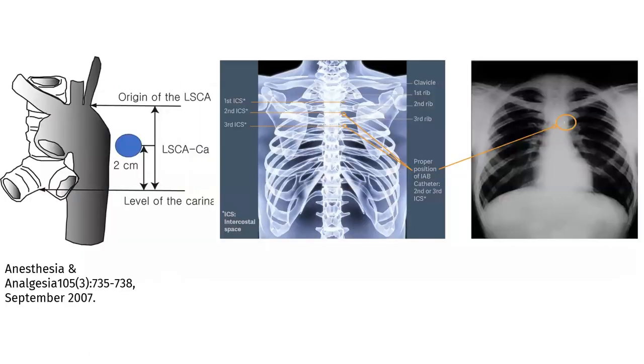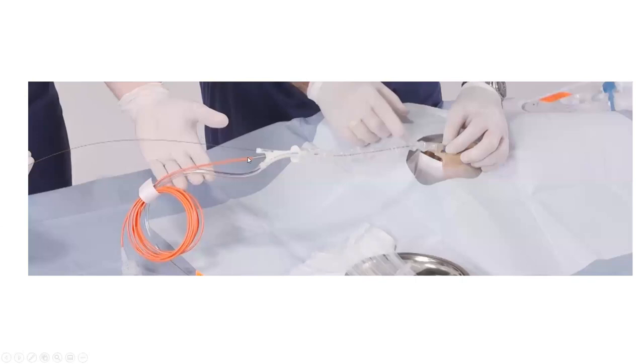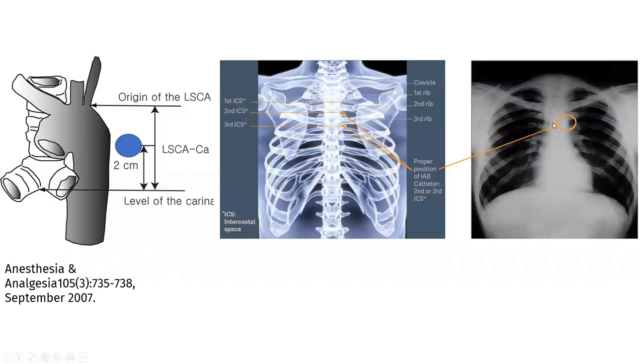Then after you get it in, you make the connection to the extension helium tubing, this here, you connect the fiber optic, and you connect the arterial line at least to a pressure bag, if not to the back of the console, as I explained previously. Now, where do you position the balloon pump? This is where you should position it. You see the carina on the X-ray, and you position it under fluoro above the carina. Typically, you should position it about 2 centimeters above the carina, but just above the carina and below the aortic arch, definitely below the aortic arch.